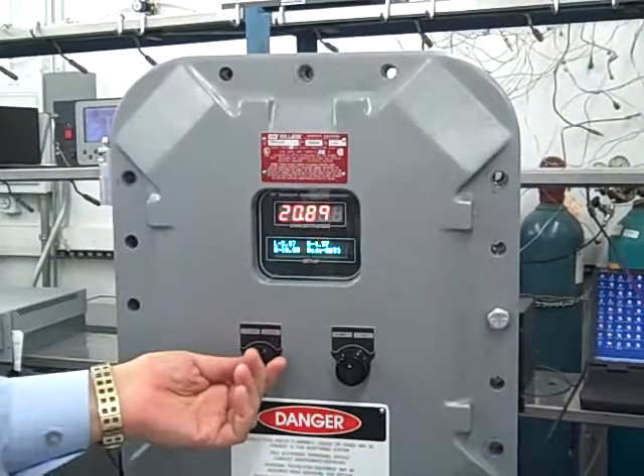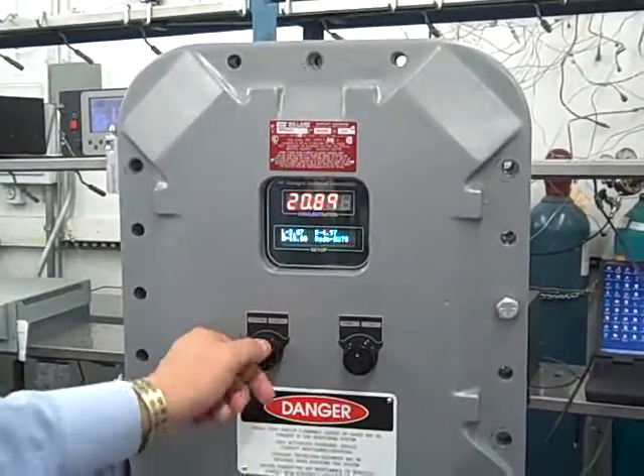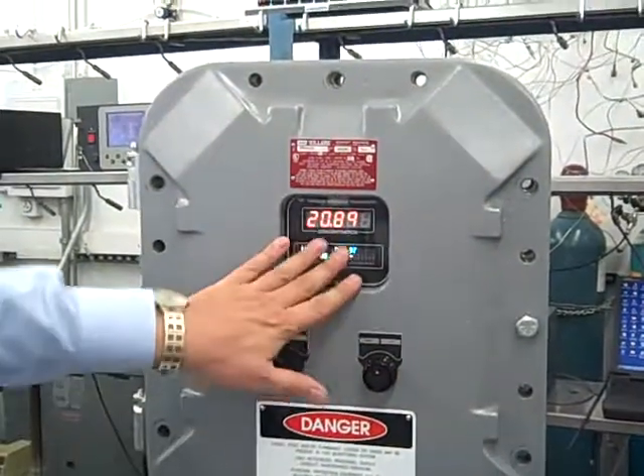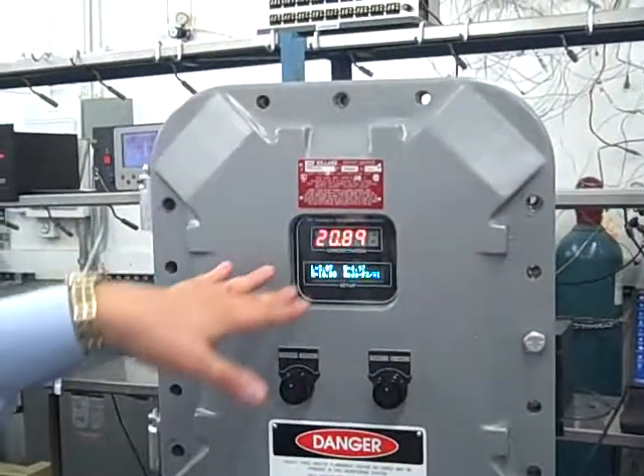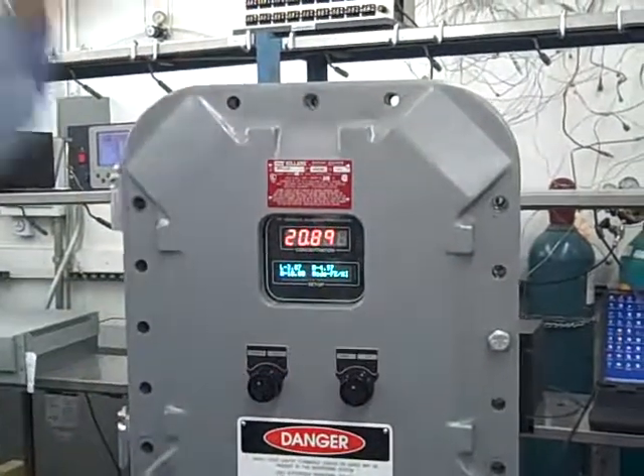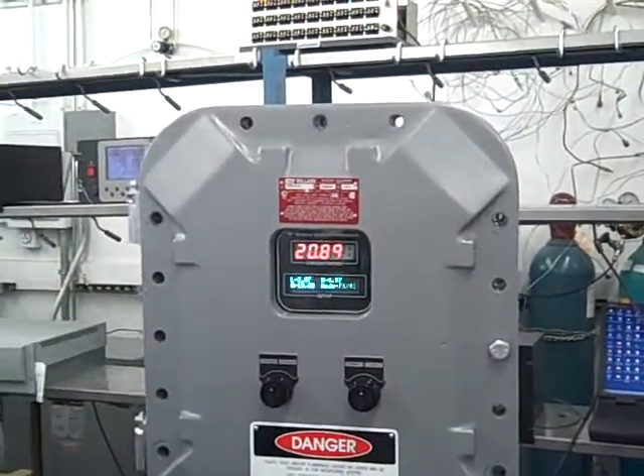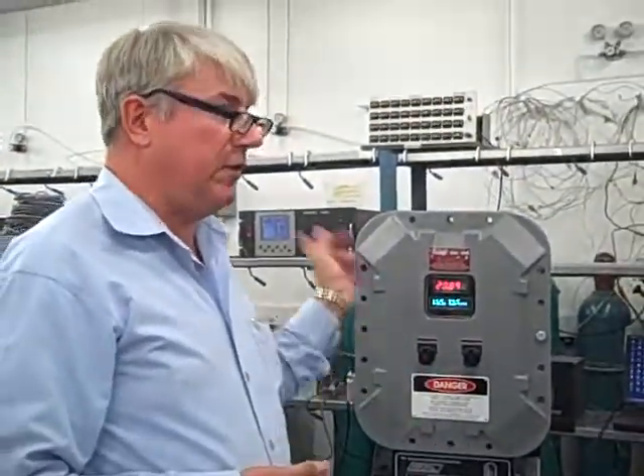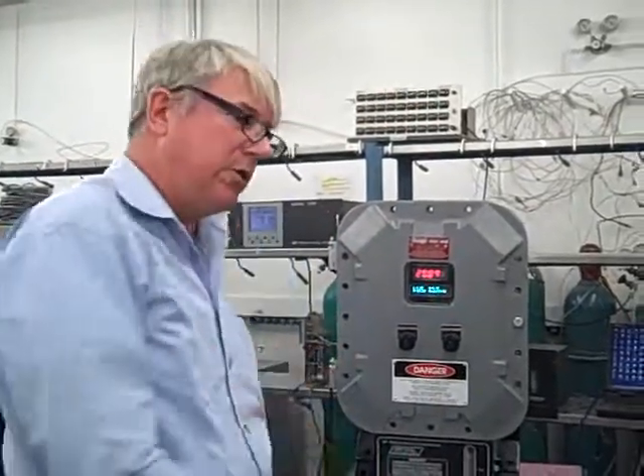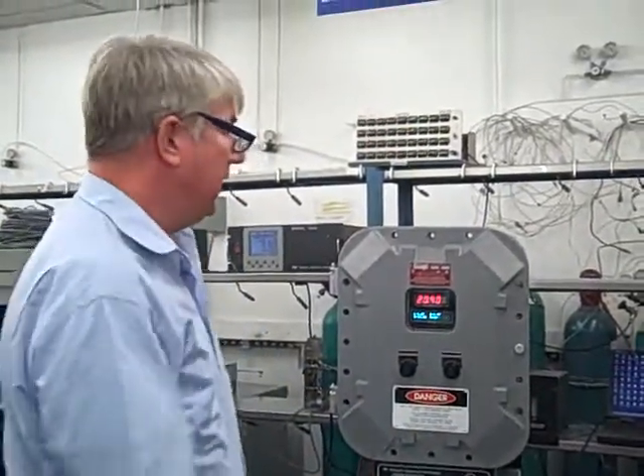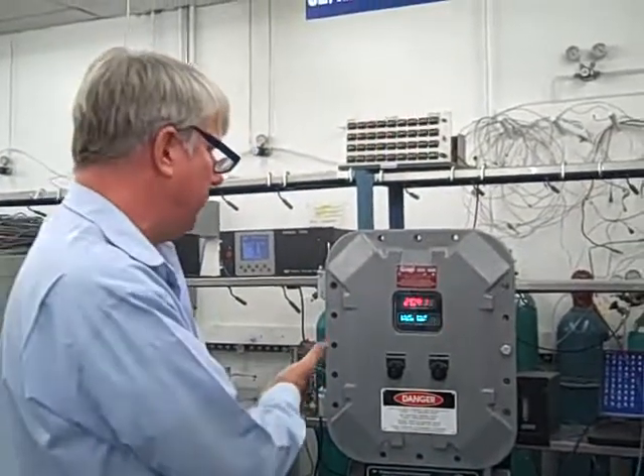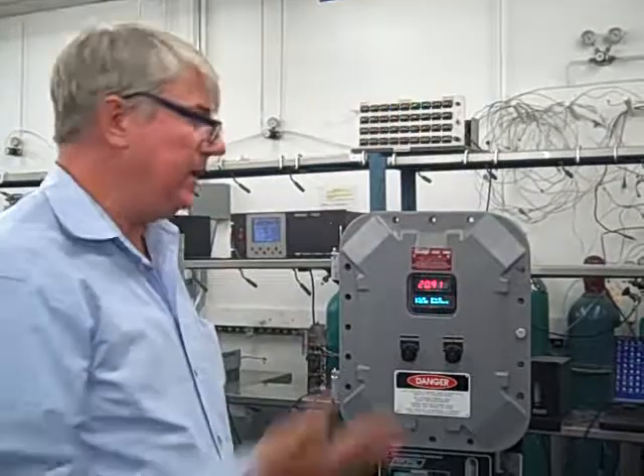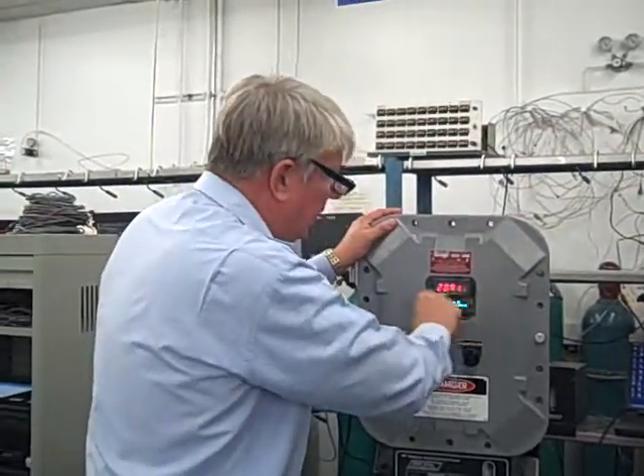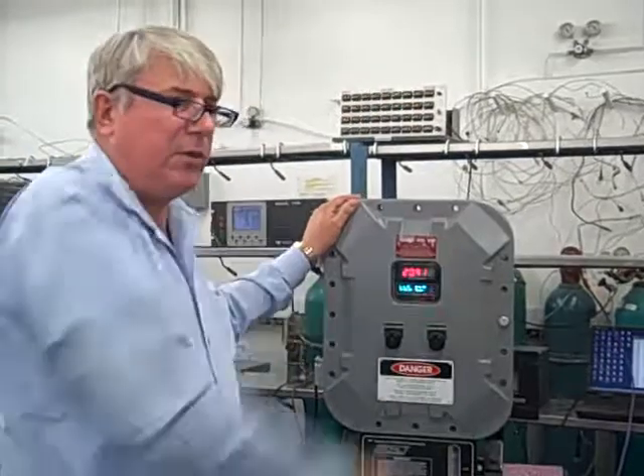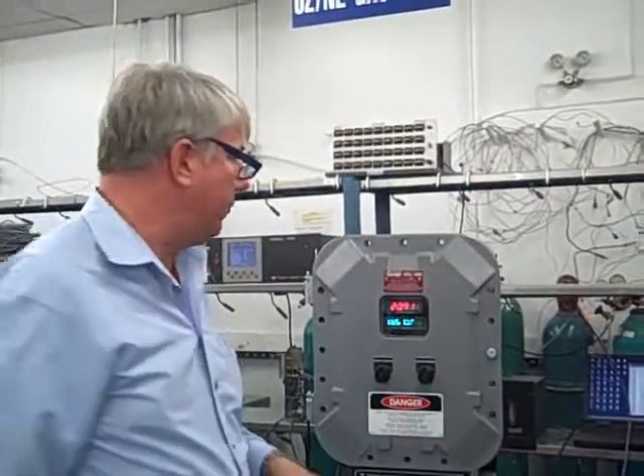Now this is probably the most important part of it, which is we can program the analyzer to change range or fix on a particular range. So the automatic range switching, it'll change the range to be what it thinks is the best range at that time for operation. For instance, if you had a low range of 1% and a high range of 25, if your reading was 24, it would go to the 25% range automatically. If the reading was a half, it would go down to the 1% range automatically. Some customers like that, some don't. It doesn't affect the reading as it's displayed here at all. It'll give the same number regardless of what the range is, but it affects the analog outputs on the back.